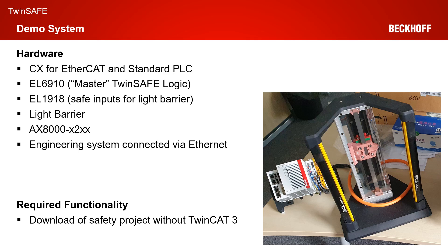The required functionality today is we want to download a safety project without the use of TwinCAT 3. Now it's time for our live demonstration. We start by scanning our hardware so that we get an EtherCAT master for the configuration. After searching for the adapters, we choose the EtherCAT adapter.